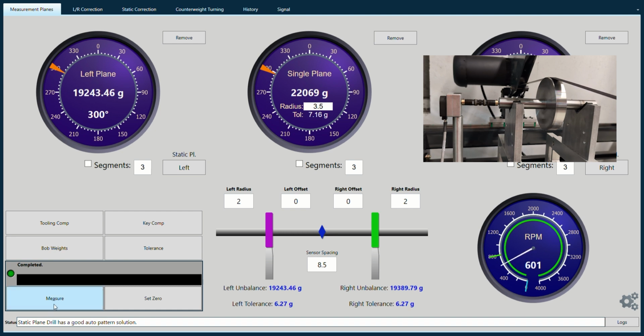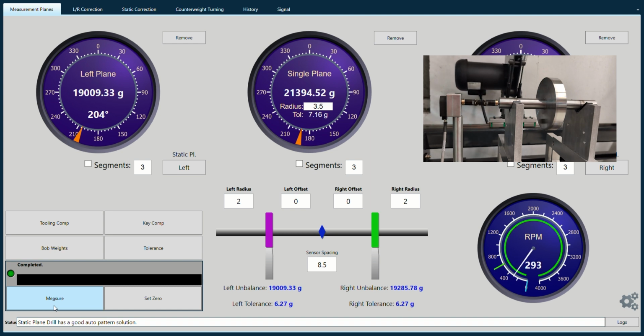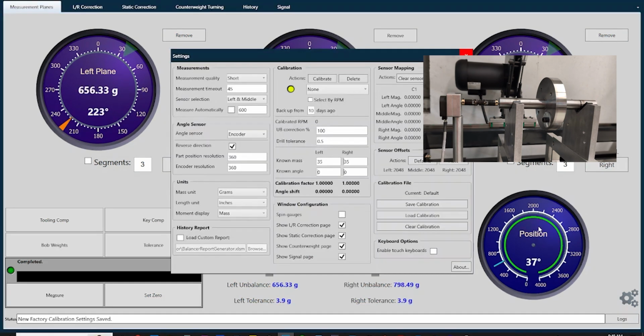With the part spinning at speed, take a measurement. The numbers on each dial will display the unbalance at that particular radius. Open the settings box again by pressing the gears icon. Locate Known Mass in the center toward the top. Enter the number written on the calibration arbor, usually around 46 grams, in both the left and right boxes.